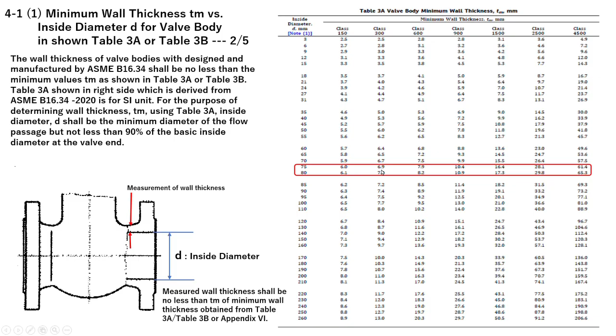So we have to calculate the minimum thickness by the interpolation method. So class 300, 6.9 and 7.0. This is between the calculated wall thickness by the interpolation method. So rewriting Table 3A, inside diameter 75 millimeter, 80 millimeter. These are tabulated numbers, so 76.2, class 300. Calculating the wall thickness with the interpolation method, we obtained 6.924 millimeter.